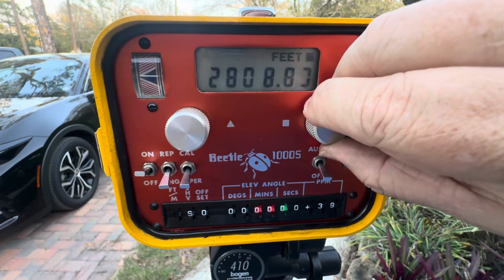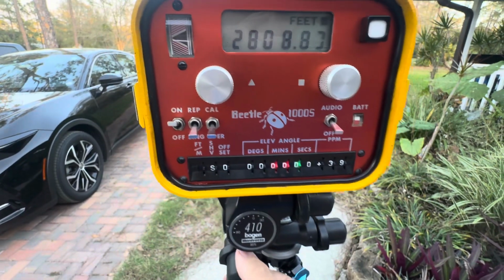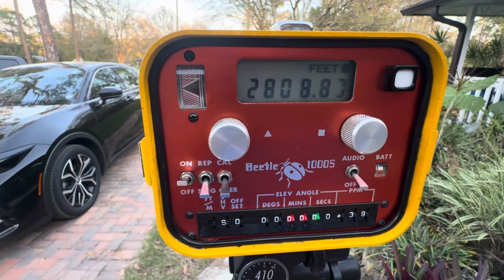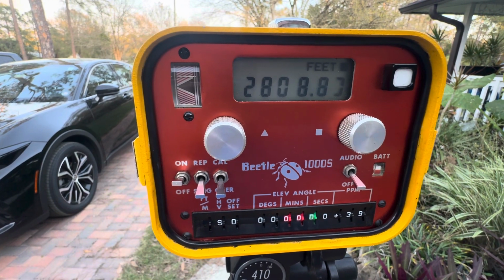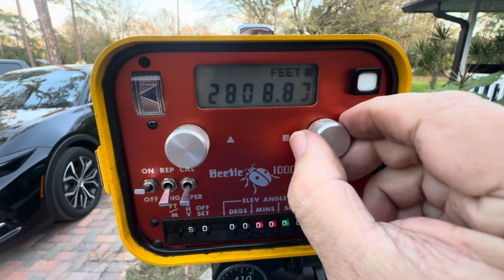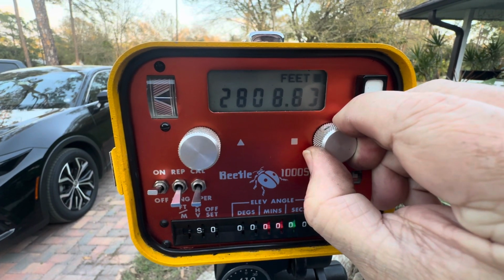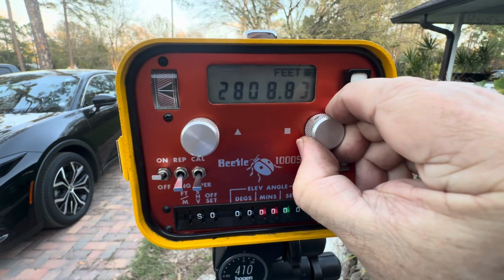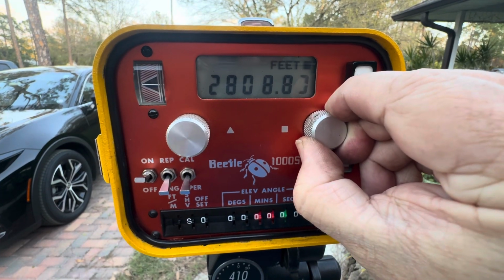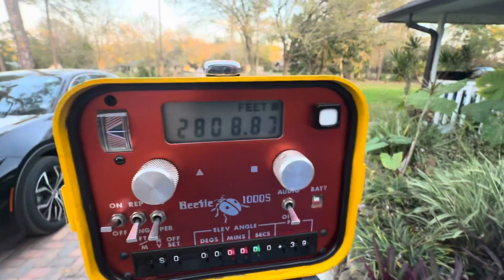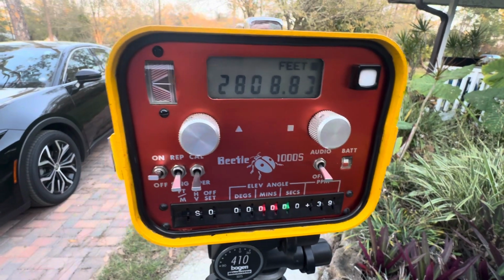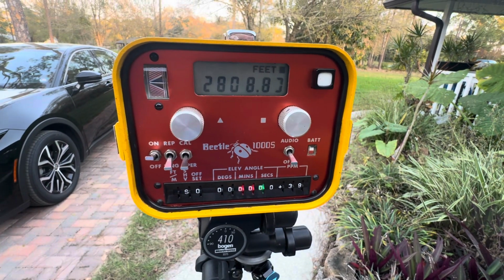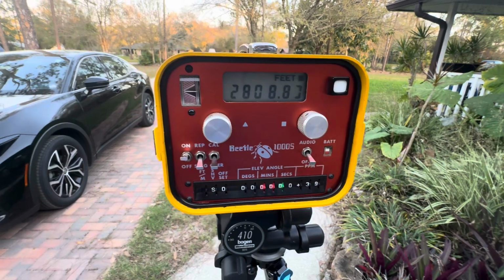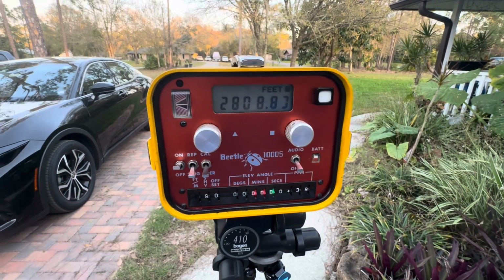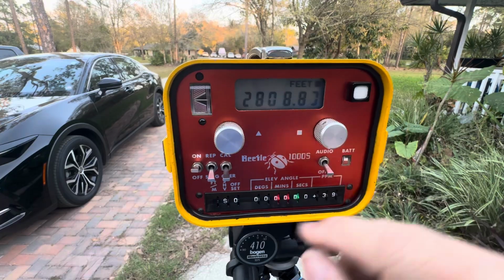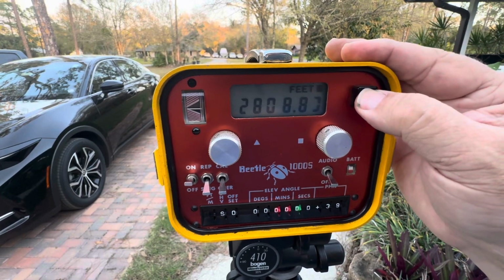And then I'm going to check the vertical here and see that I could do a little more there. So I'm going to bring this down back to the point. And we want it to be right at the point in the same spot we had the calibration, because during a reading, it flips between the calibration circuit and the read circuit and compares the two. So we're going to fire off a single reading by pressing the button.